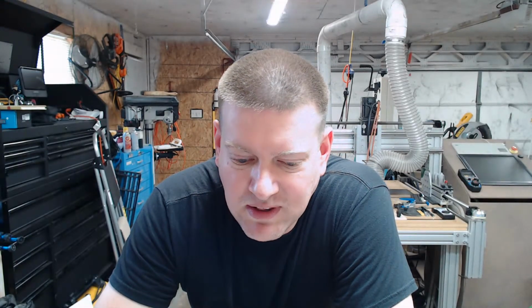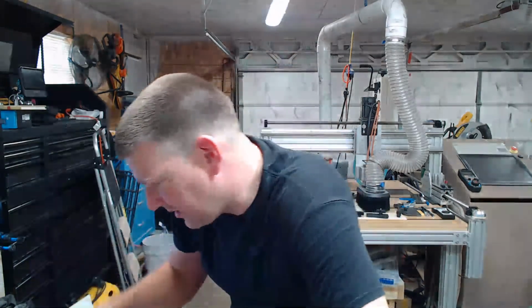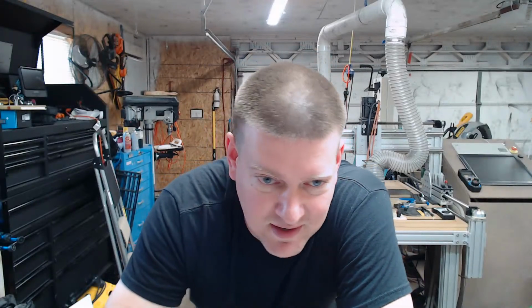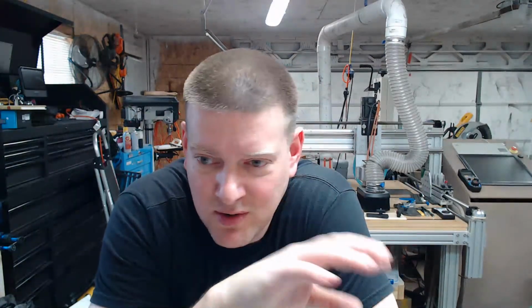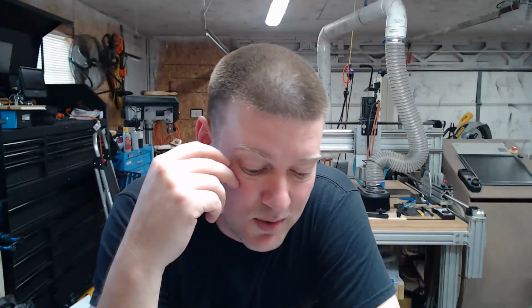Bjorn, you're asking for a video about LIMs. Yes, in fact I just found another line isolation monitor tester, an older one. I had one here that I tore apart on video, but I found another one, an older one, and it looks like it's in excellent condition. So I have 2 brand new ones from Bender, and one older one, and it would be really neat to compare and contrast the technology between them because it is different for sure. The older one looks like it's a little bit easier to use, but the newer one has so many more options for testing, like L1 to ground, L2 to ground. You can fine tune everything. It's like a calibration device for calibrating your LIM display. So it's a very cool setup, and I do want to do a video on those.